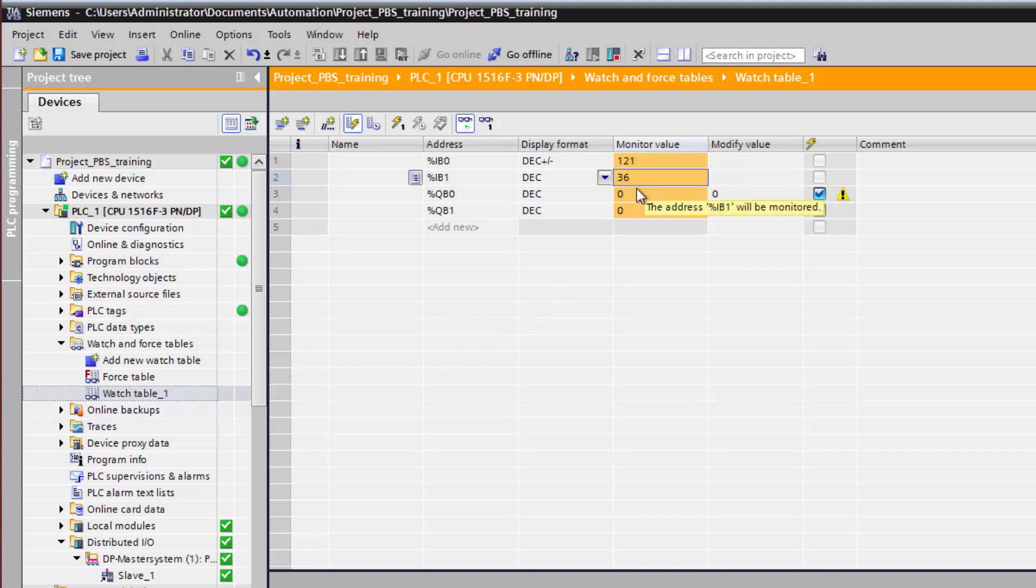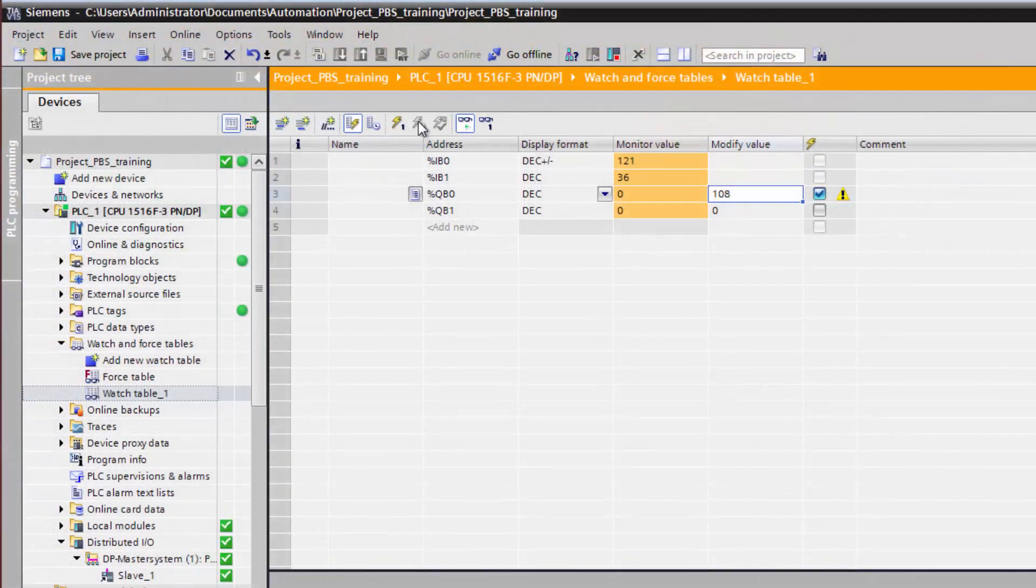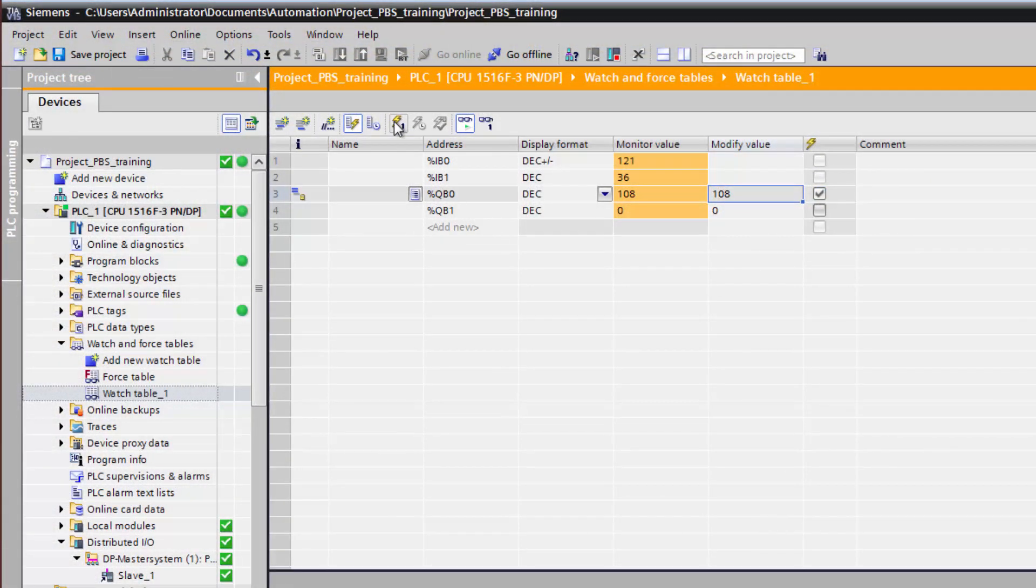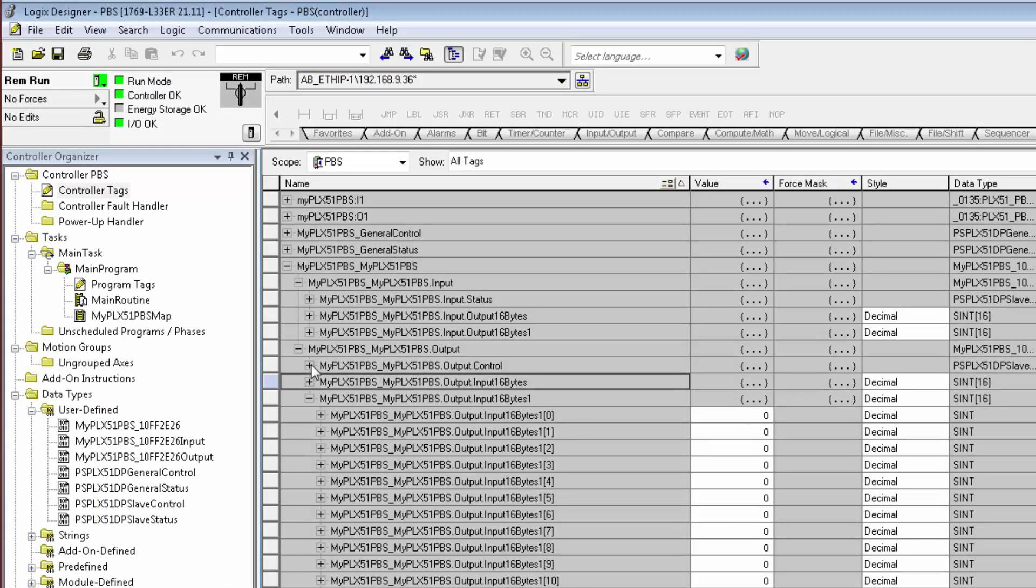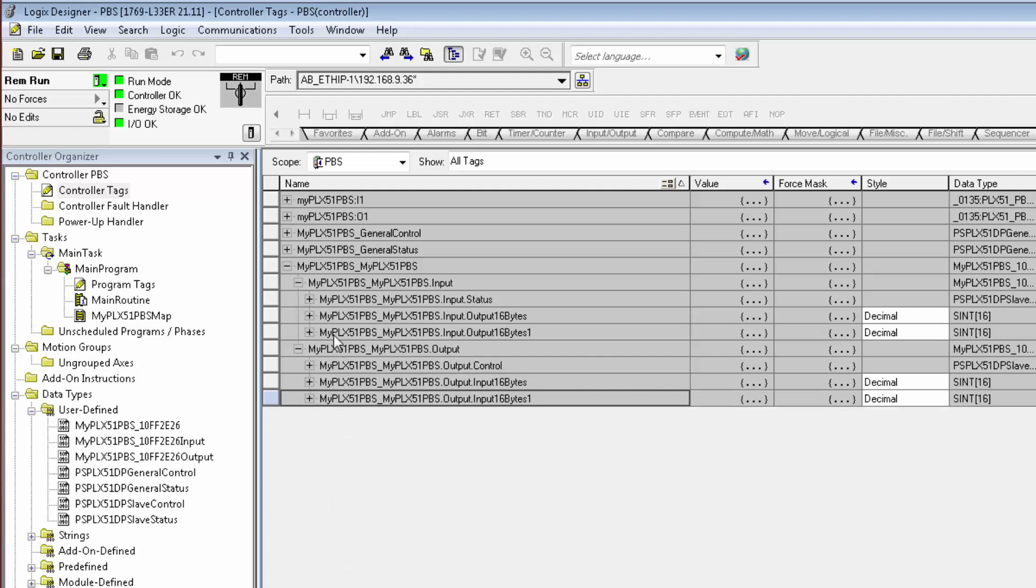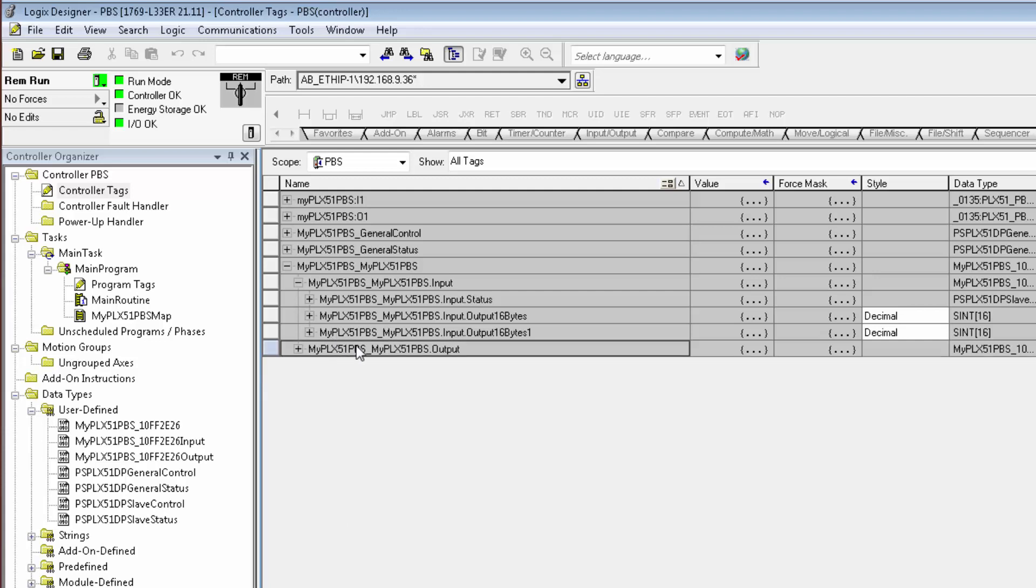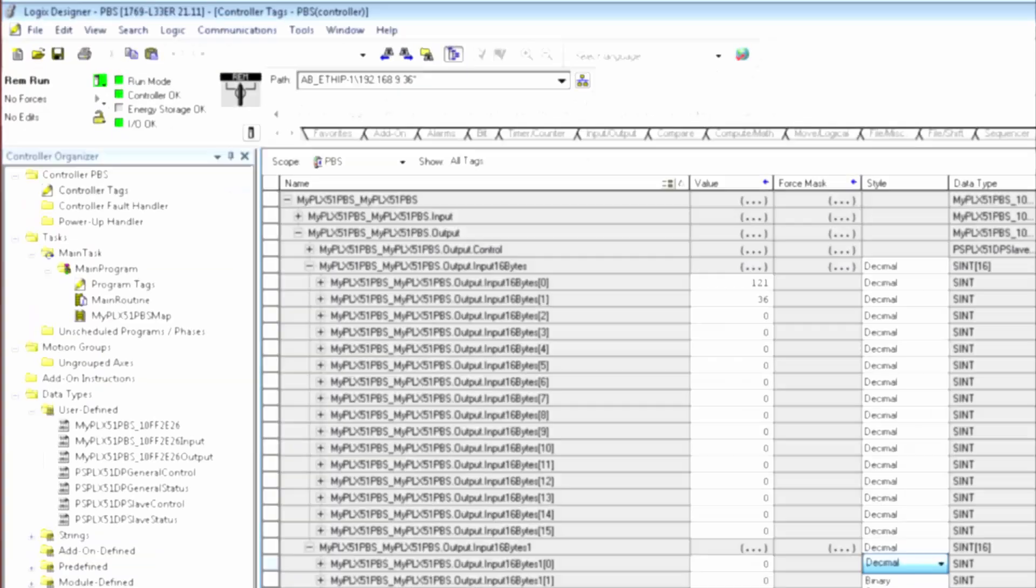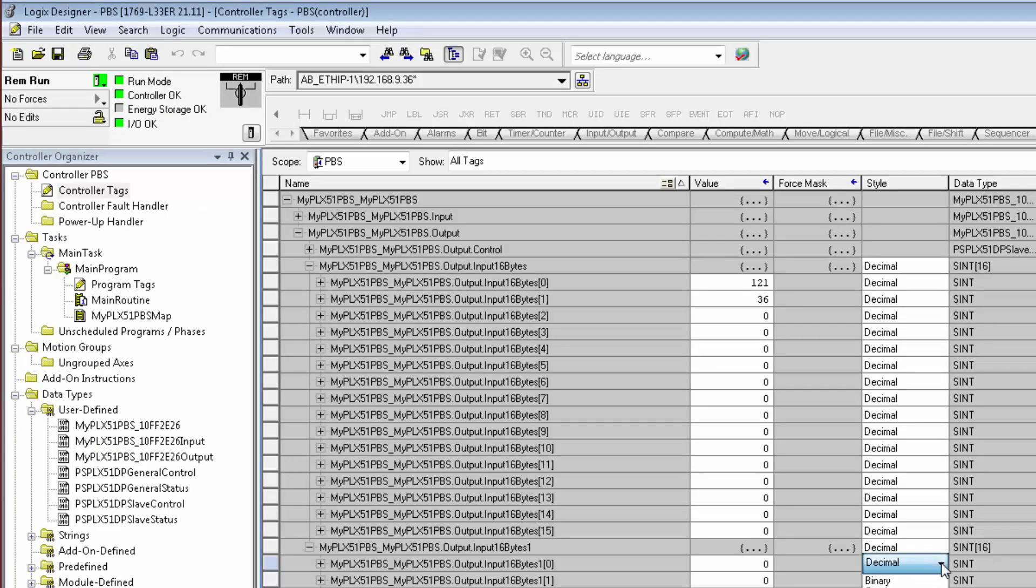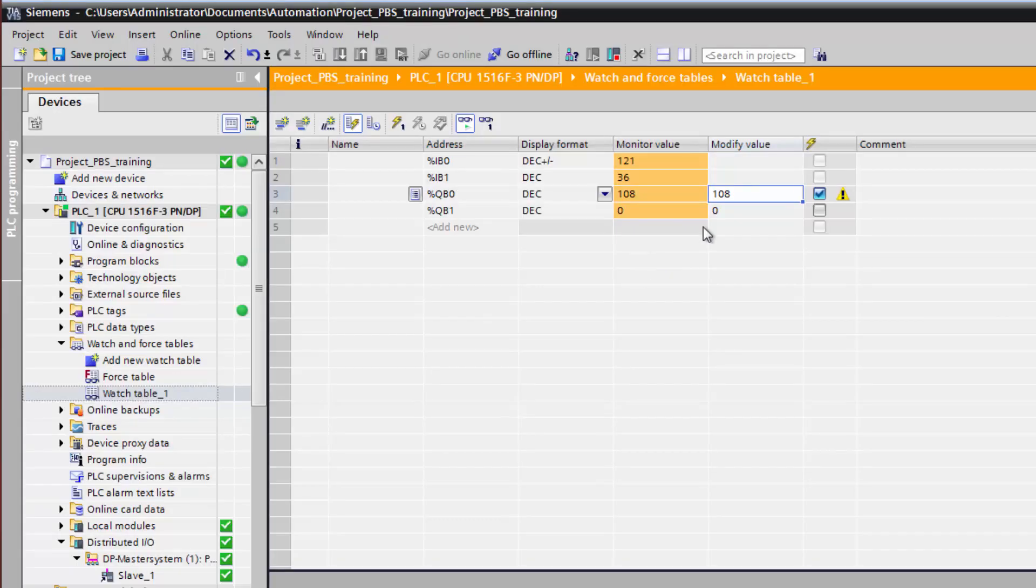Conversely, if I enter an output integer in the S7 watch table, I can return to Studio 5000 and I'll find it in the input output tags. So this is data coming from the S7 PROFIBUS master being written to our gateway and then to our CompactLogix. So just remember, on the Ethernet IP side, inside Studio 5000, the input and output label is reckoned for the Ethernet IP side of things. It will be the opposite for the master on the PROFIBUS side.